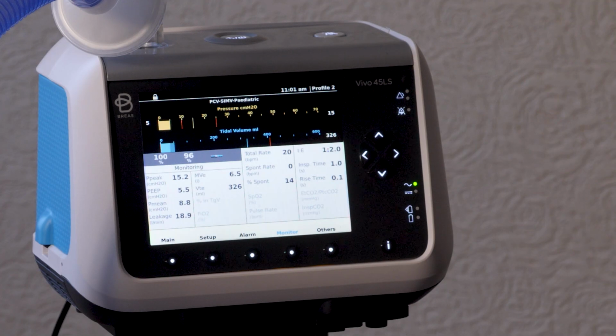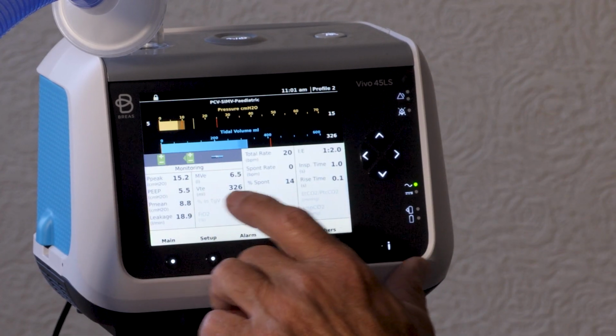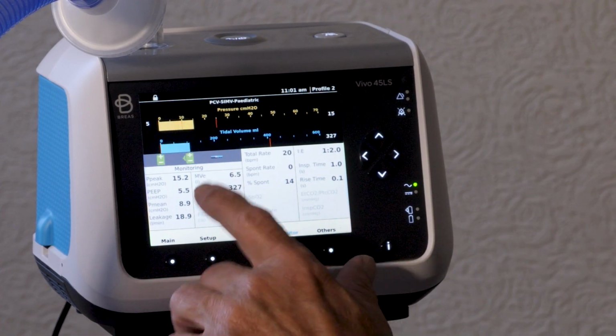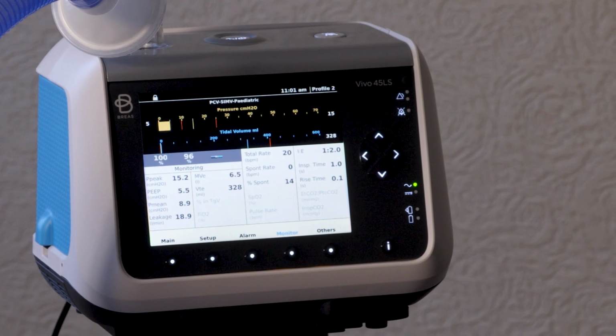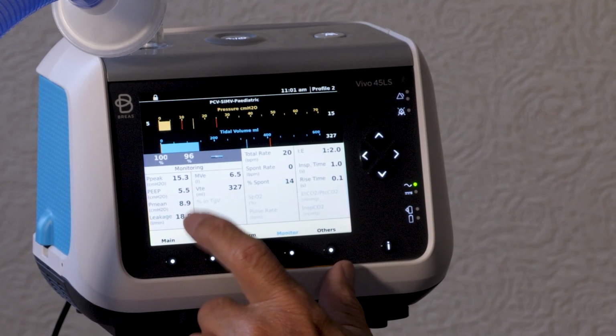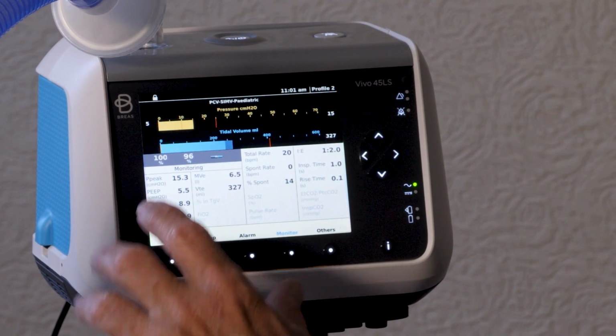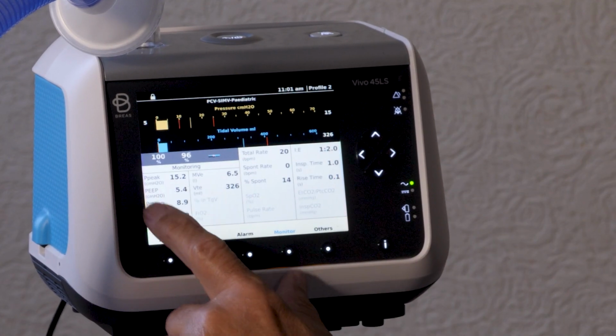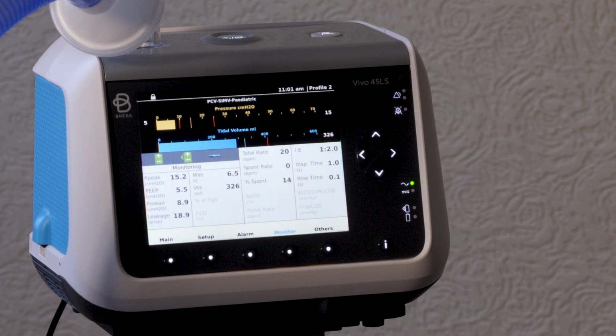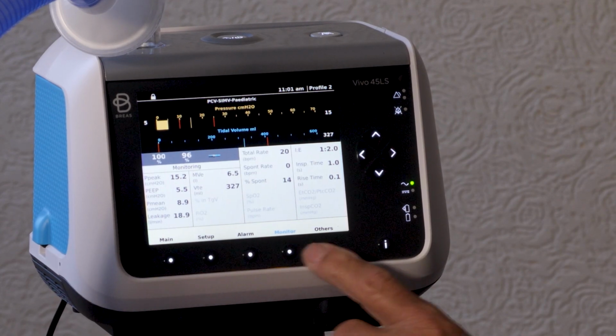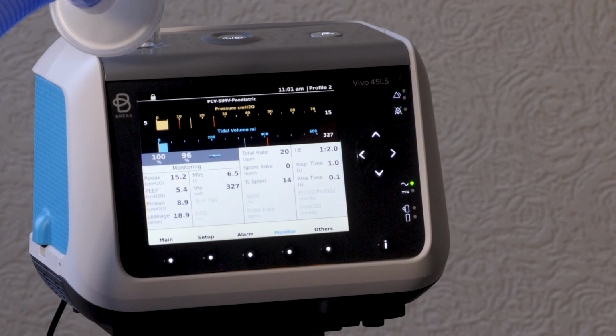It gives you your tidal volume, which is the amount of air per breath that's being moved into the patient. In this particular case, it measures what's being exhaled, so it's your exhaled tidal volume. And then it tells you, as far as your leakage is concerned, how much leak you have here. It also gives you a reading on your peak pressures and your PEEP. So it's a very informative screen, and that's what's recommended that you have on when you're using the ventilator at home.